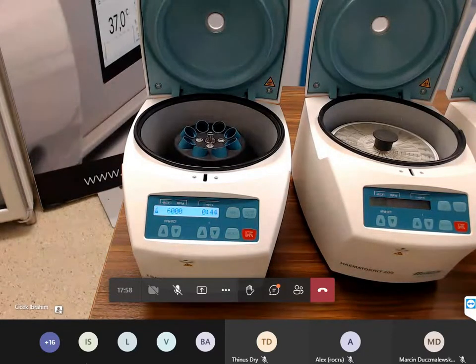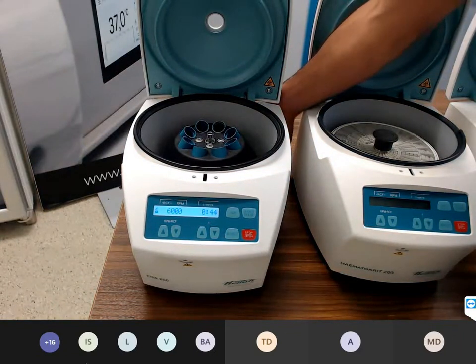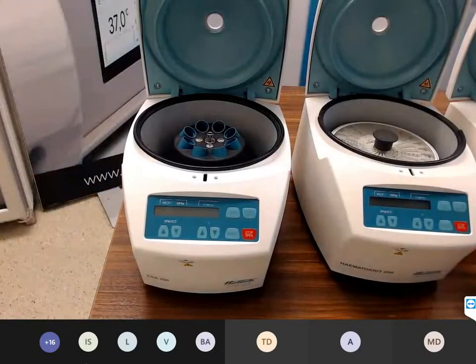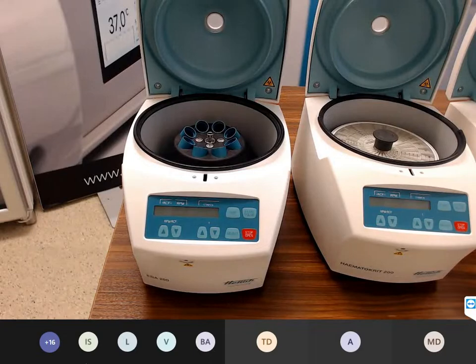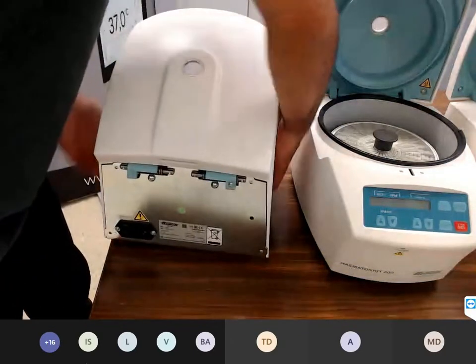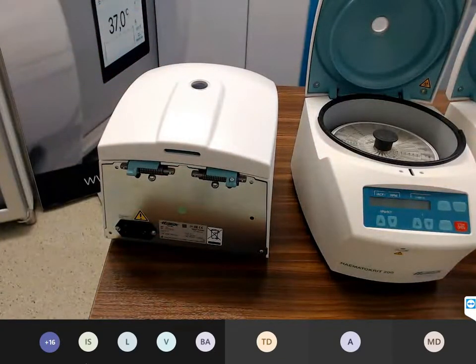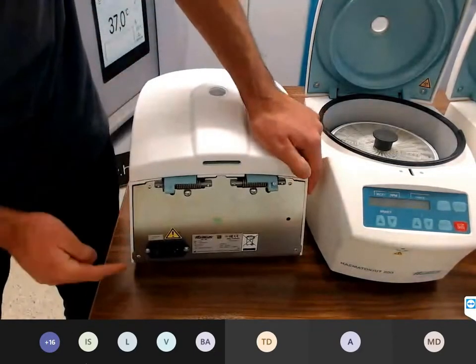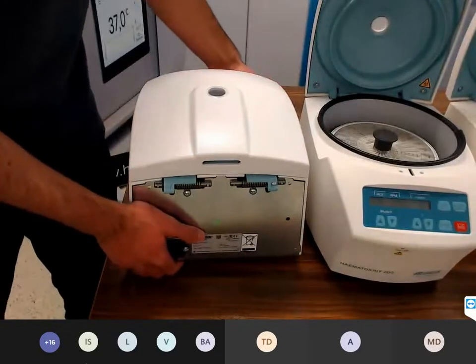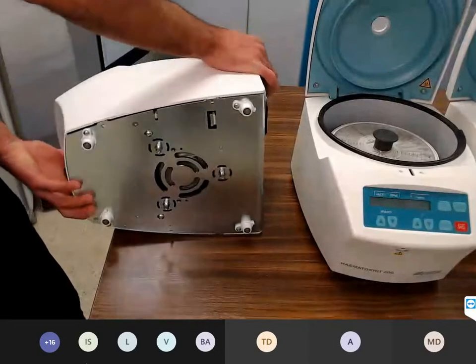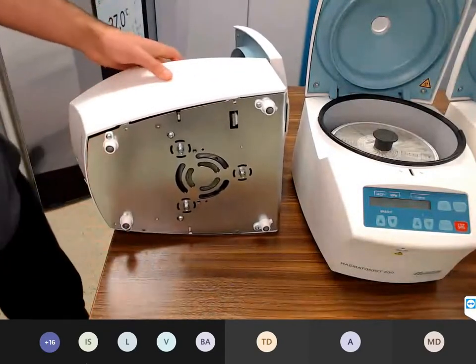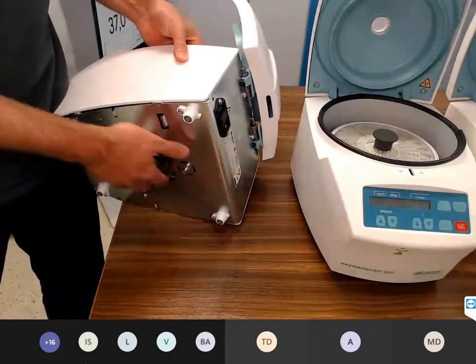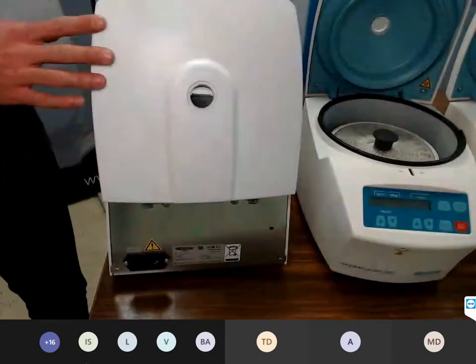Now we go into the centrifuge. For this, switch off the device, unplug it. In case of a repair, unplug it for your own safety. We have on the back side 4 screws, 1, 2, 3, 4, and also 4 screws on the bottom side. Remove the screws, and then you can remove the upper part, the white part.